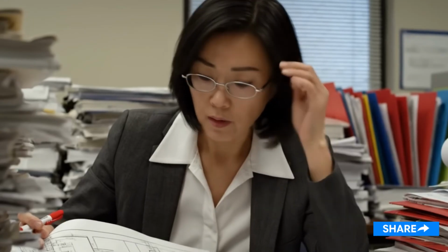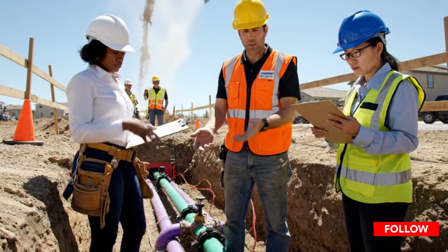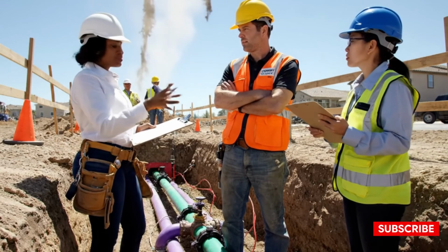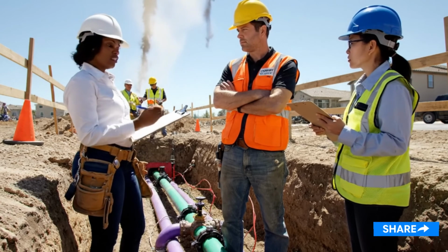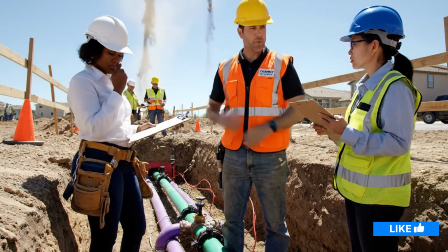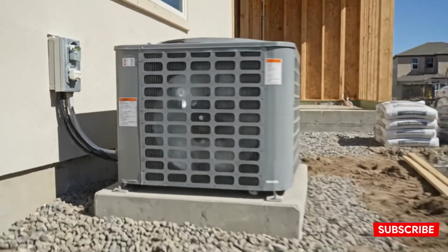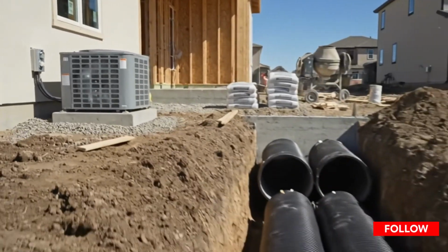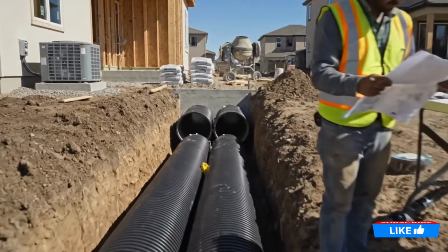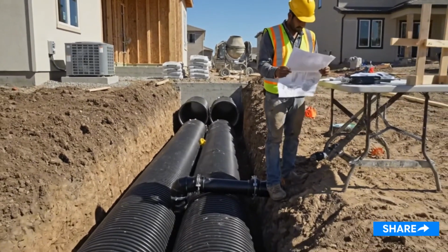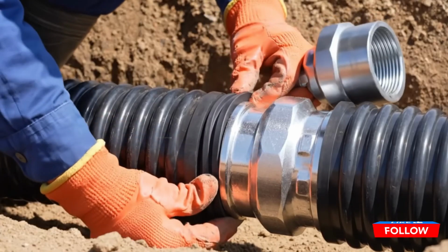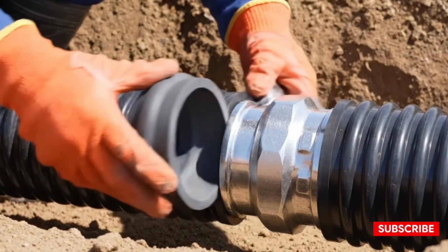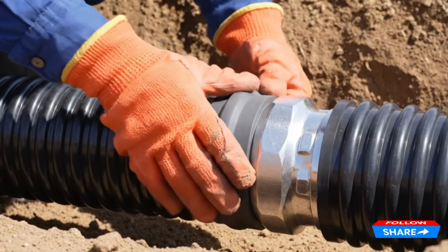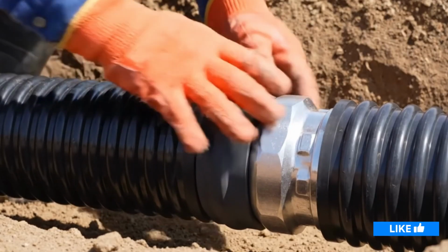First, the homeowner would need to understand local conditions. Soil type matters, climate matters, groundwater depth matters, radon risk matters. Clay-rich, moist soils tend to transfer heat better than dry, sandy soils. A high water table can complicate excavation. In extremely humid climates, the practicality of direct air tubes can drop significantly because dehumidification becomes an even bigger problem than temperature itself.